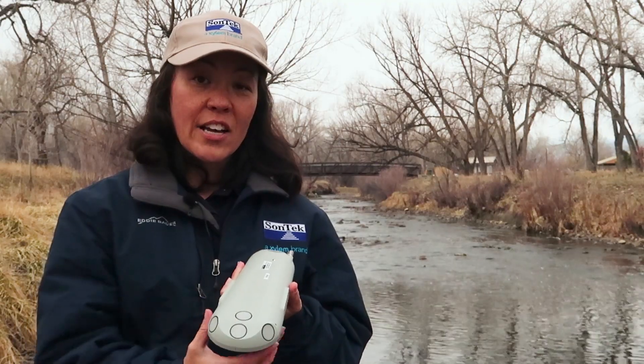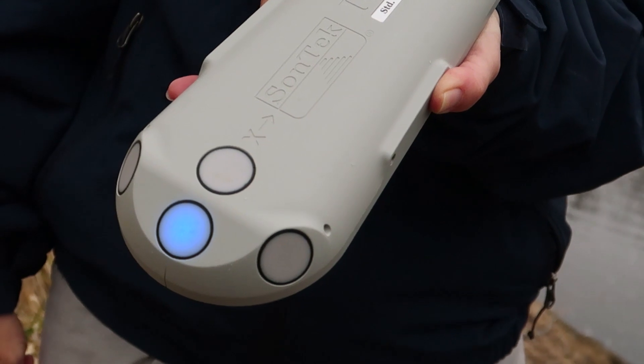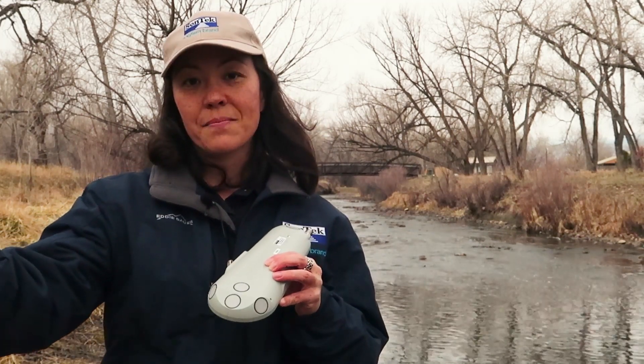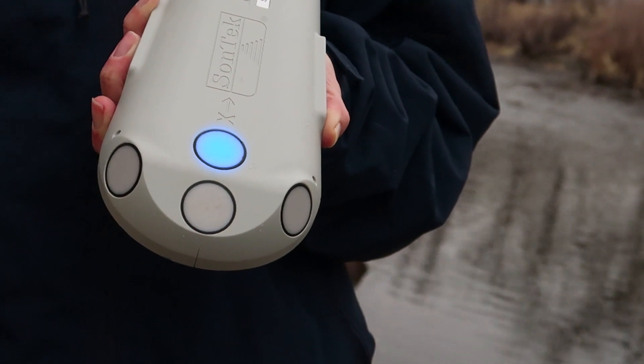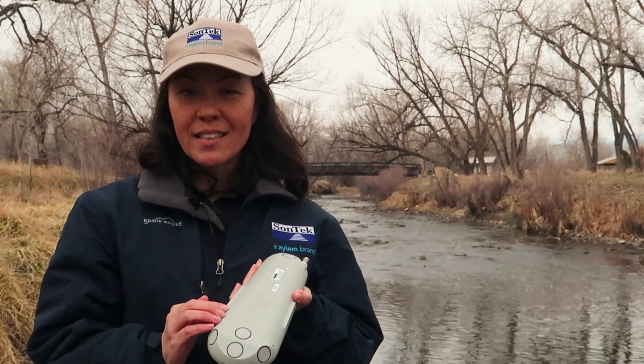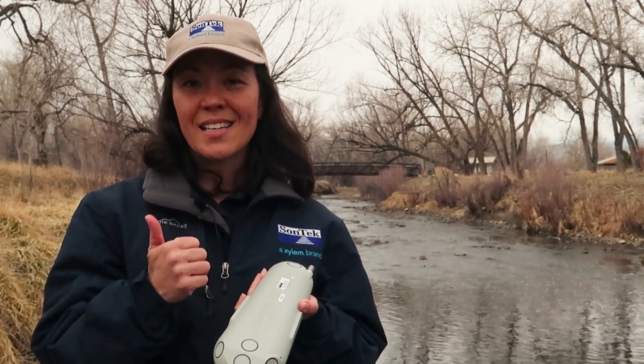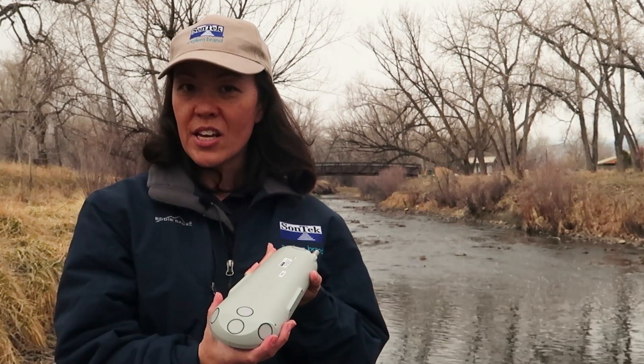You'll also notice that the SonTek IQ has five acoustic beams. It has a set of beams to gather data right in the center of the river, but it also has skew beams that look out to the side, so you're gathering data all the way from the center out to the banks — giving you all that data for the best flow calculation possible. There's also an acoustic sensor for water level, plus a pressure sensor. Both are redundant sources of water level data, and they work together to calibrate one another for the most consistent, robust water level data possible.